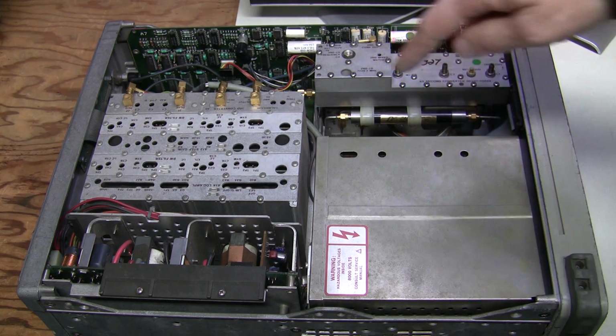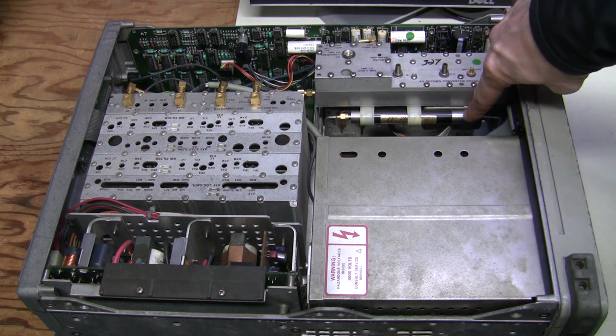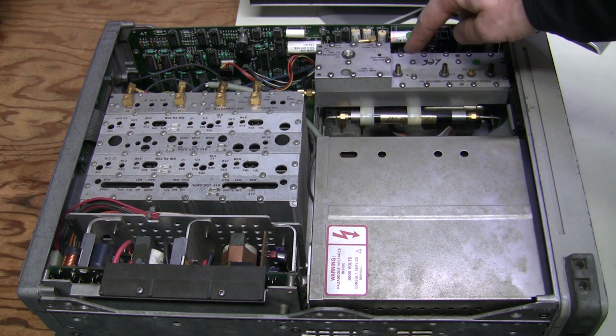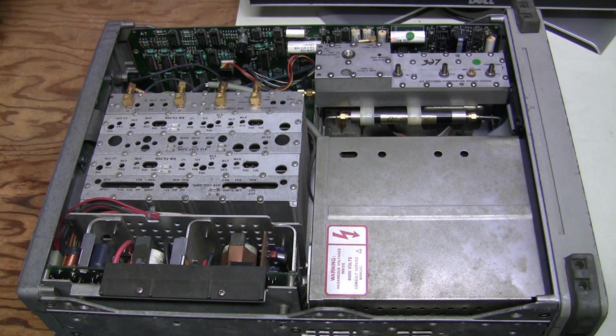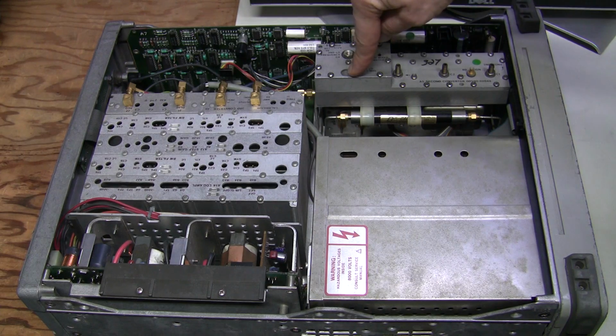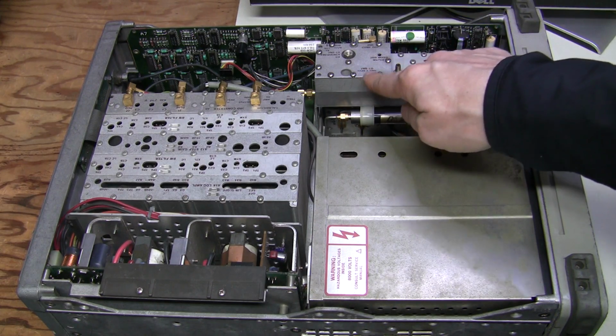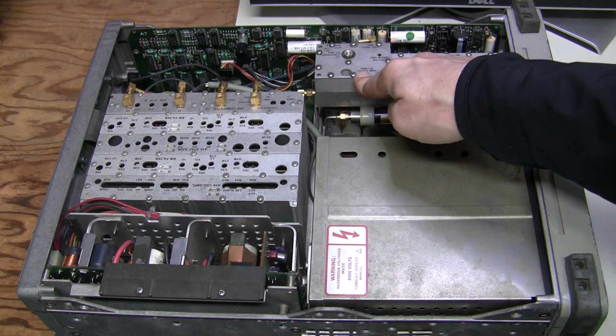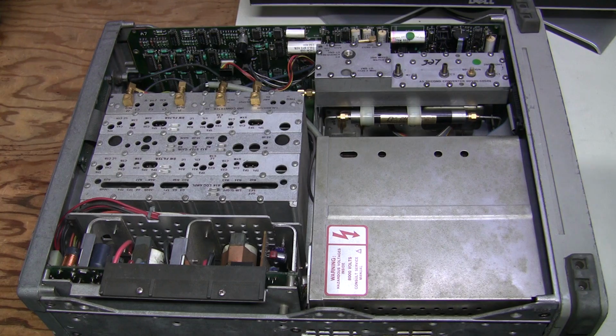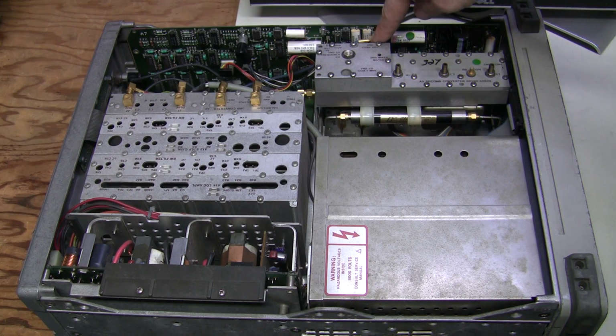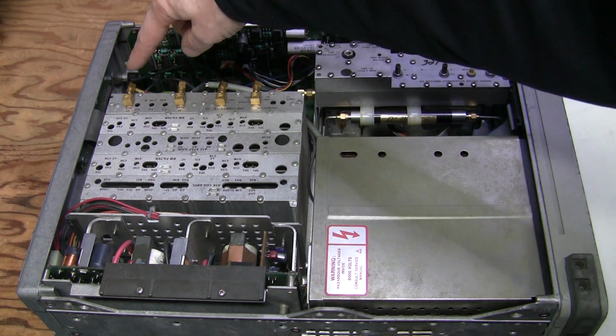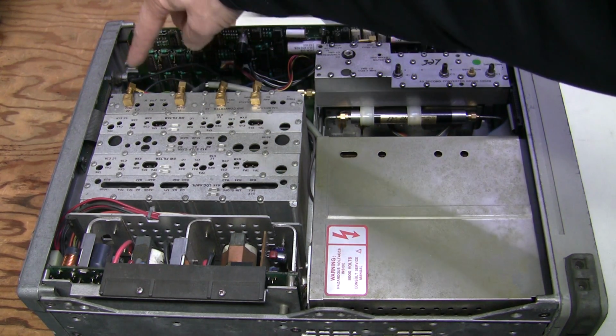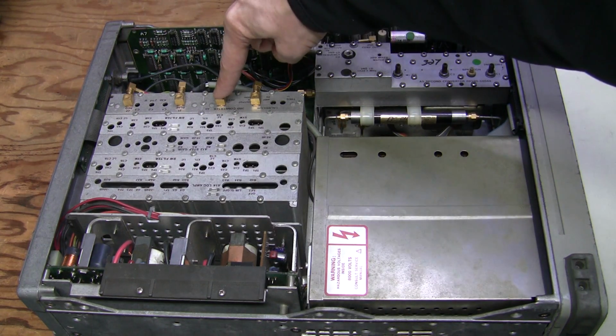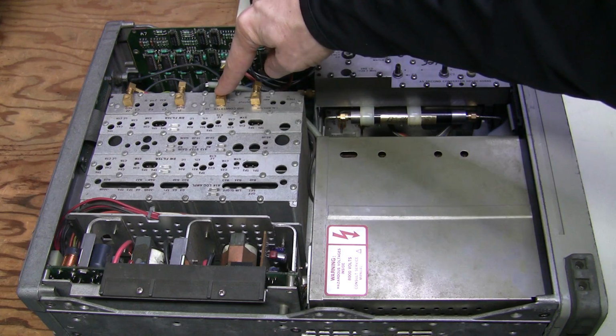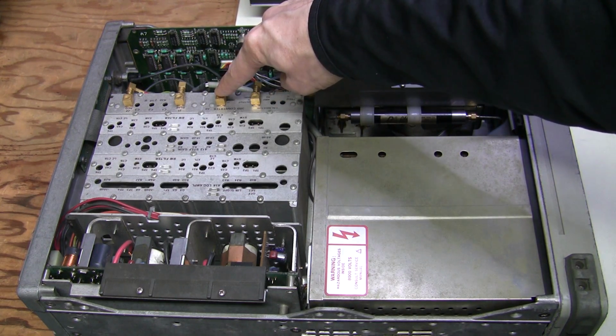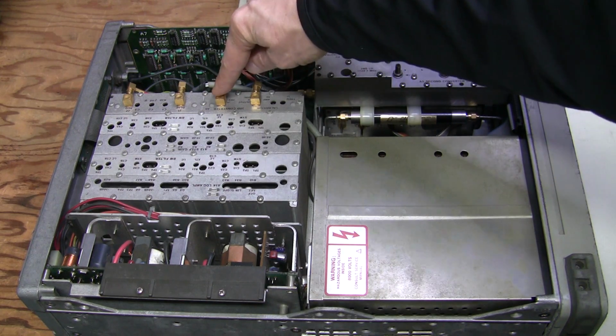Then the signal goes from the first converter through this low pass filter to the second converter, where it is converted to 1.7 gigahertz. Here is a connector to check the second LO, and unfortunately I cannot check that as well. It is 1.7 gigahertz. This is the output from the second converter. It goes to this point, to the second IF. This is the output of the second IF, goes here to the third converter, and at this point the signal should be 321 megahertz, and we can check that.